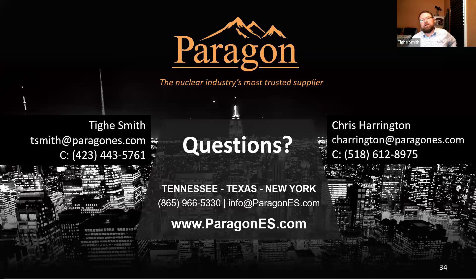A follow-up question based on our answer about OPG: when you repair a PC board, have you essentially taken over the OEM and their liability? Do you have the OEM's consent? Part of it is we take over the Part 21 responsibility when we do the repair. We don't necessarily take over the OEM liability from that standpoint, but we do adopt the design control aspect of it as part of our repair. That's how we assure that it's going to meet the form, fit, and function equivalent.